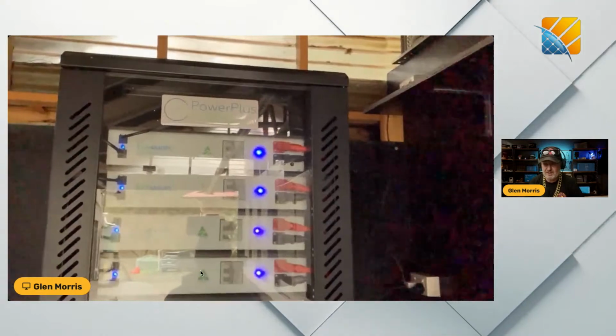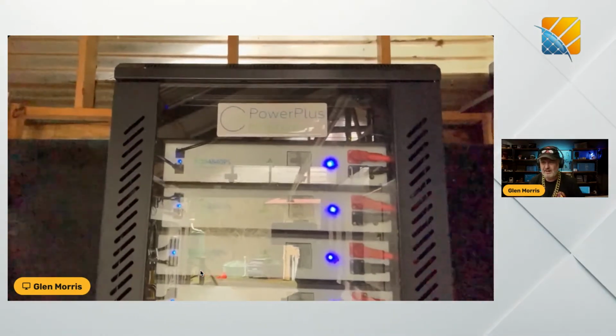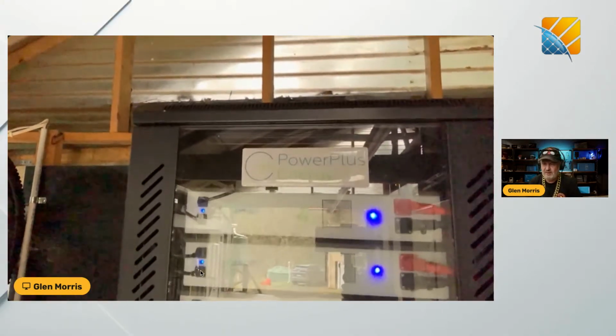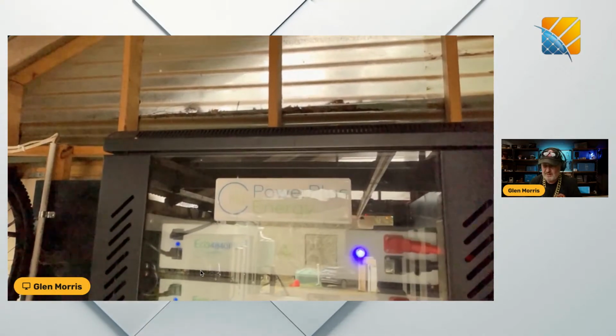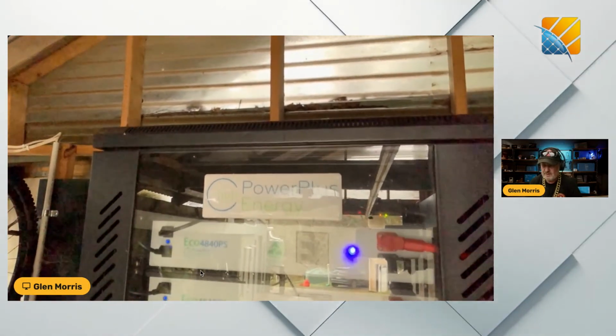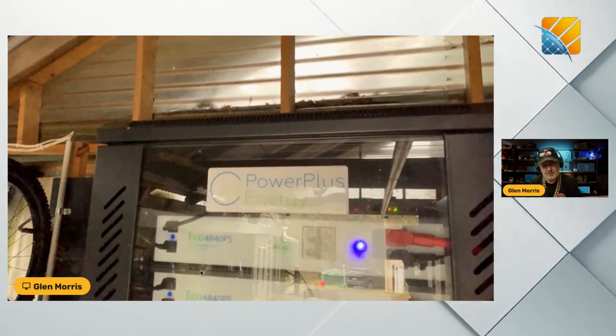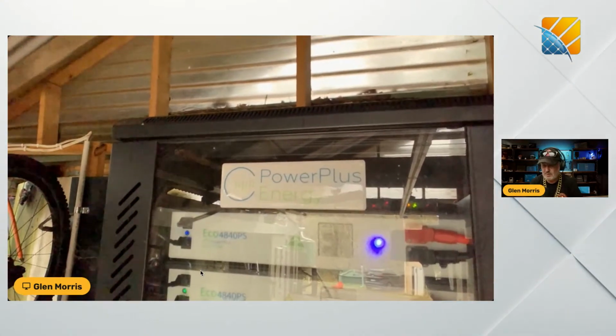So to shut down the system, the shutdown procedure lists turning off isolators 1 through 20 on the battery module, after you've turned off all the AC and the inverters. There's also a little box up top, the PowerLink, a bonus feature they've got here so we can monitor it through the cloud.